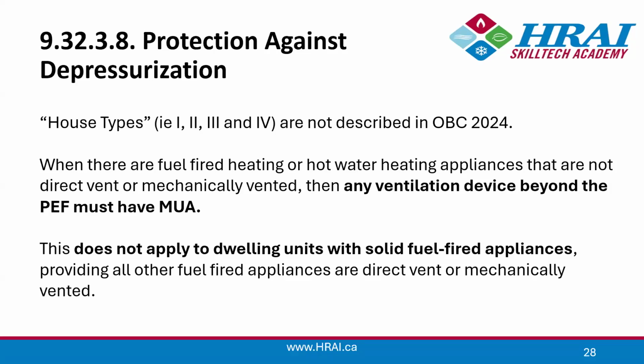So this does not apply, however, to dwelling units with solid fuel-fired appliances, providing all the other fuel-fired appliances are direct vent. So if you've got a direct vent appliance plus a solid fuel-fired appliance, you don't need that makeup air provision. So it's only when you have a not mechanically vented and not direct vent appliance. A B-vent appliance would be, I guess, the best example. You've got a gas log set with no glass. That would be a problem. Any of those are going to get really sticky with makeup air.